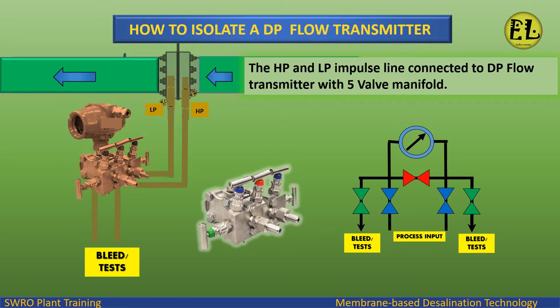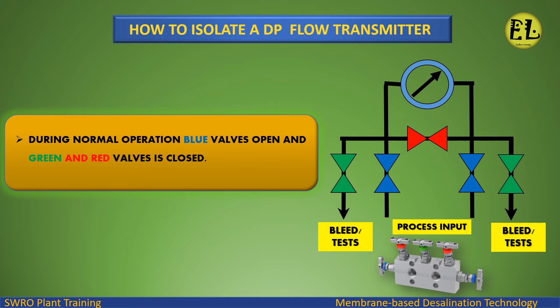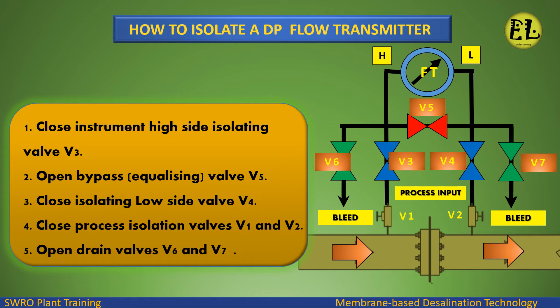The high pressure and low pressure process impulse lines are connected to the DP flow transmitter with a 5-valve manifold. During normal operation, blue valves are open and green and red valves are closed.